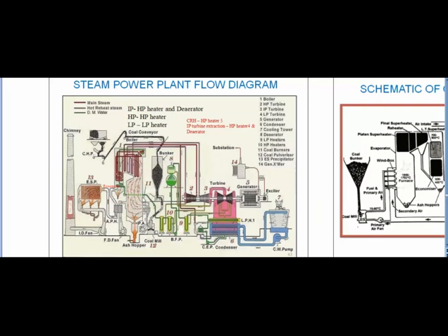The wall of the furnace is made up of water wall tubes. The heat released by the combustion of coal is absorbed by the water wall tubings. Feed water is supplied through the downcomers and bottom ring headers to the water wall tubes by which this furnace wall is constructed.